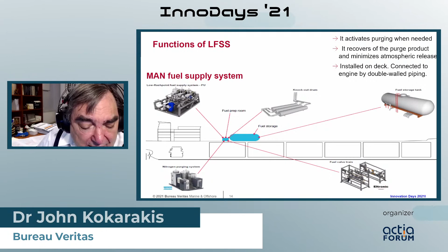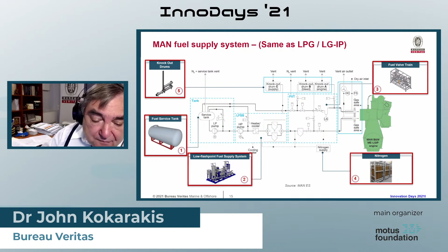Fuel supply system consists of fuel preparation room with the supply pumps and the nitrogen purging system, the knockout drums, fuel valve train, and the storage tank. Low pressure and high pressure fuel supply system with return from the engine and supply at about 70 bars. The fuel valve train and the double supply pipe within the engine room.